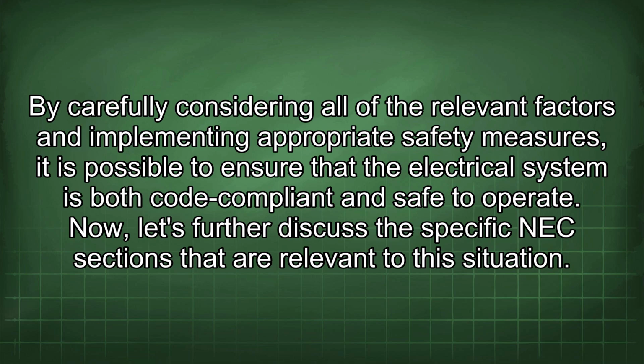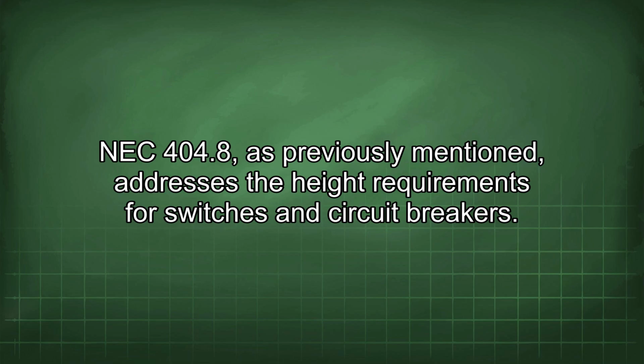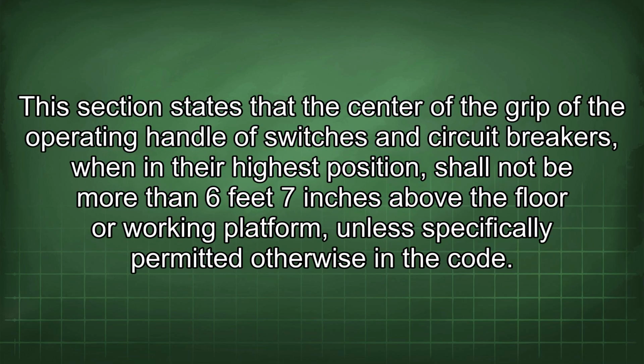Now let's further discuss the specific NEC sections that are relevant to this situation. NEC 404.8, as previously mentioned, addresses the height requirements for switches and circuit breakers. This section states that the center of the grip of the operating handle of switches and circuit breakers, when in their highest position, shall not be more than 6 feet 7 inches above the floor or working platform, unless specifically permitted otherwise in the code.